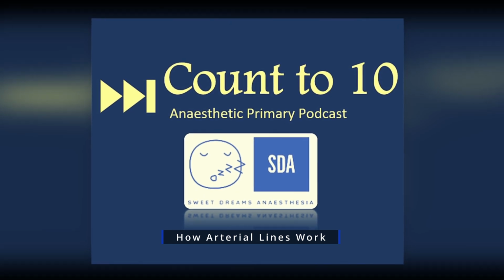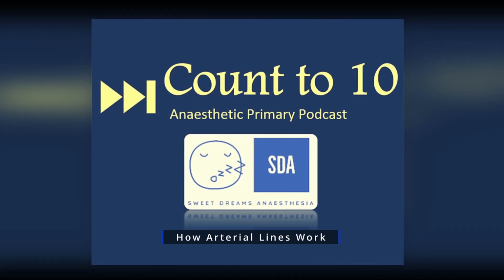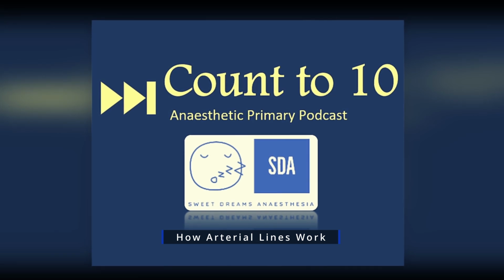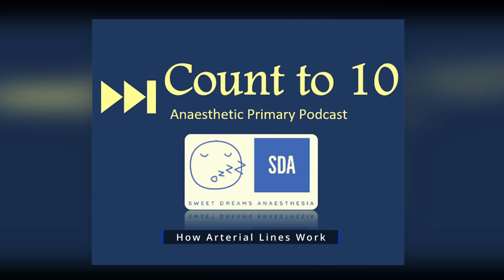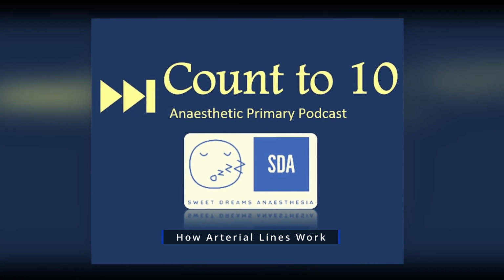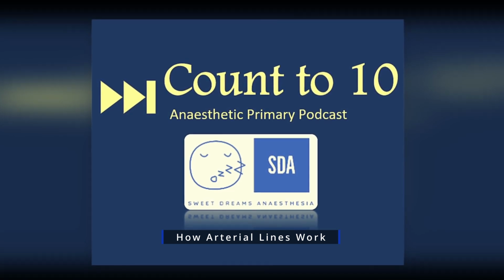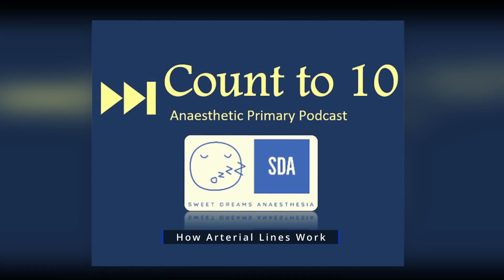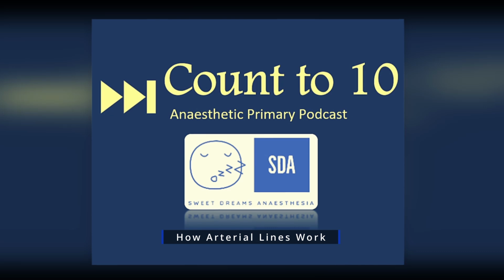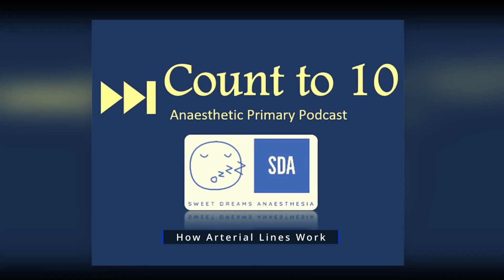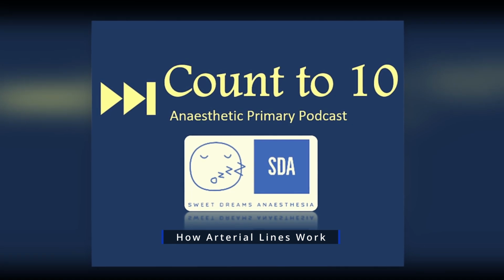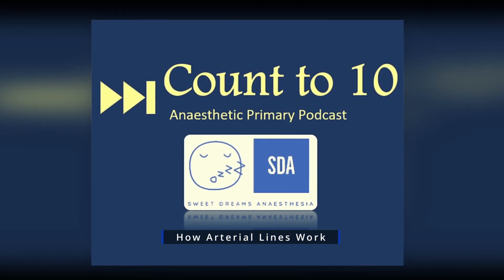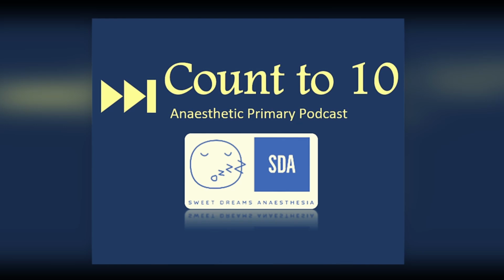So what happens once you do have an electrical signal? Well, that electrical signal needs to be manipulated in a way which shows us numbers and a waveform. The way it does this is by going through a microprocessor. The key thing to understand is that an arterial wave isn't just one waveform. It's multiple little waves of varying amplitudes. And very similar to how a BIS module works, an arterial line microprocessor uses a Fourier's analysis to reconstruct those multiple little waves into one waveform that we see.